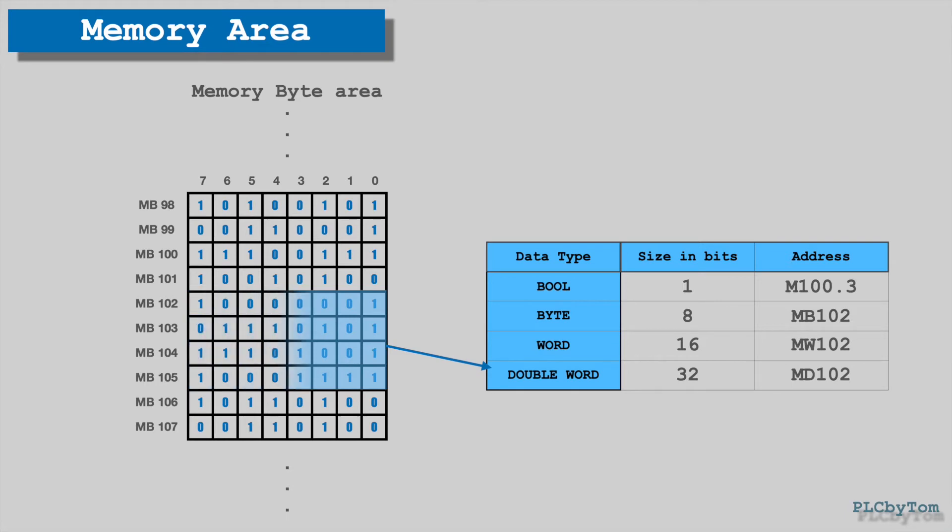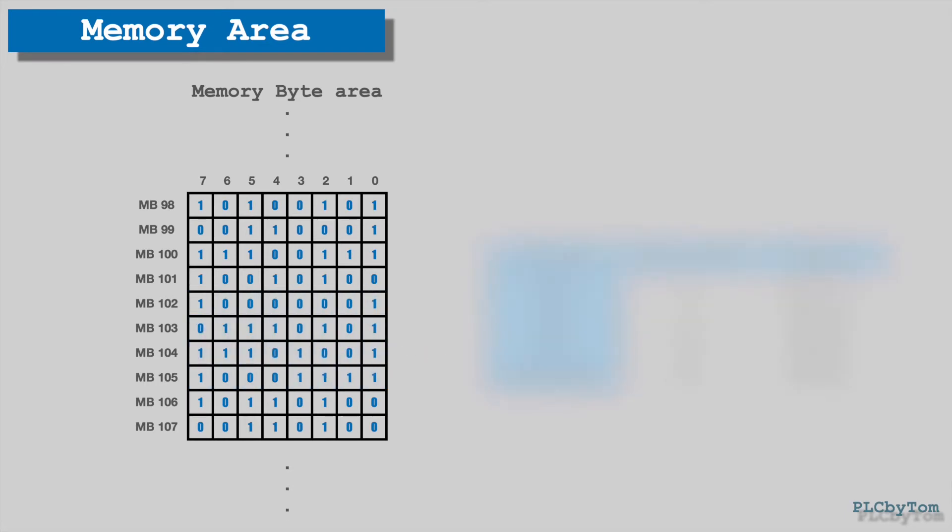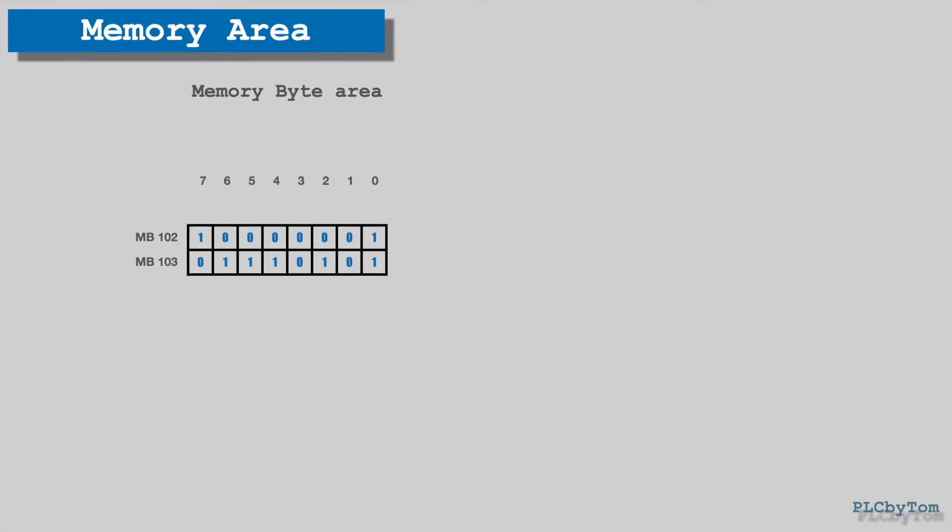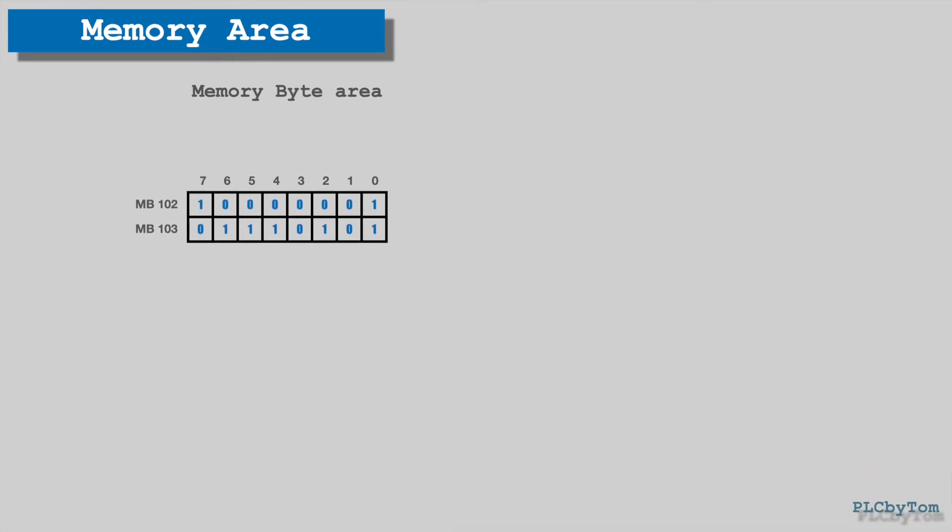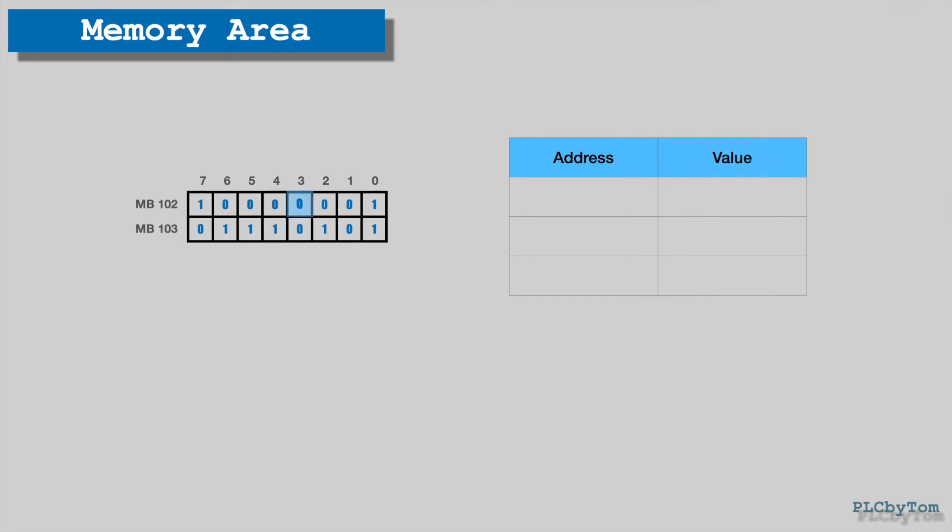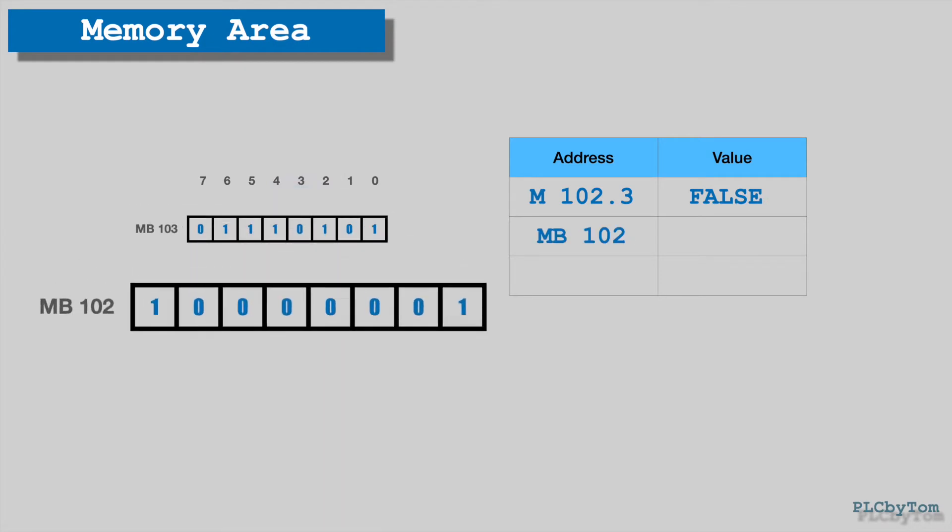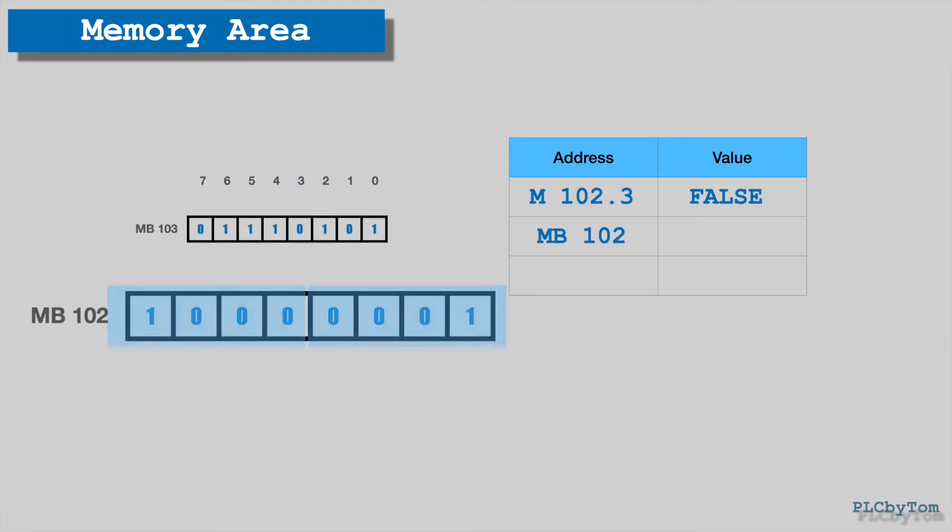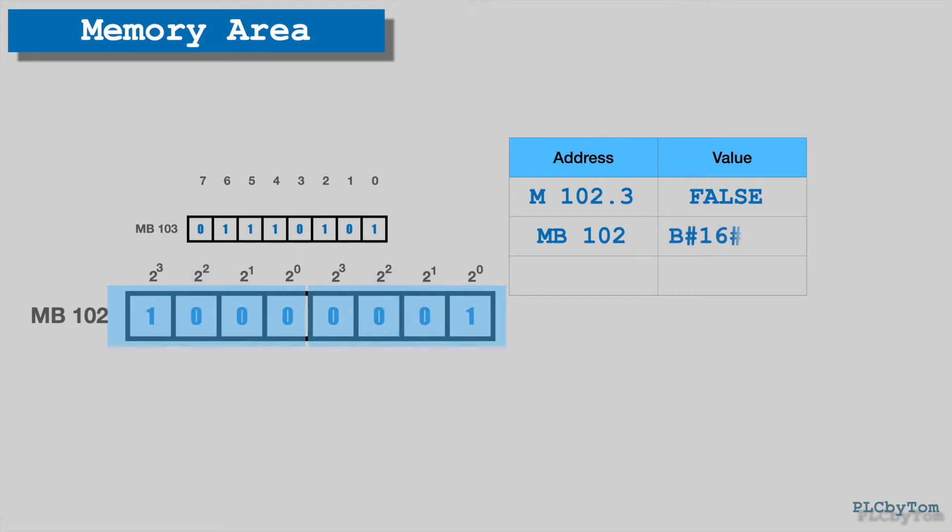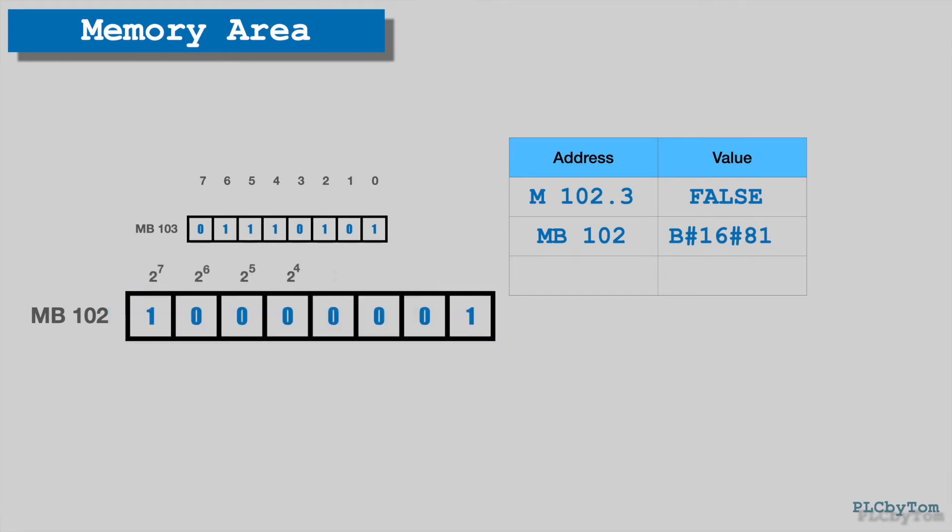Now when we understand how memory is organized and how to access the specific location of memory by addressing, we can read content of addressed memory location. By shown example there is accessing to the byte 102 and bit 3 by address format M102.3, and the value of this memory location is zero or logically false. Access to the entire byte MB102, it is read a binary value which is presented in hexadecimal format, and it is 81 hexadecimal, or represented in decimal format it is 129 decimal number.